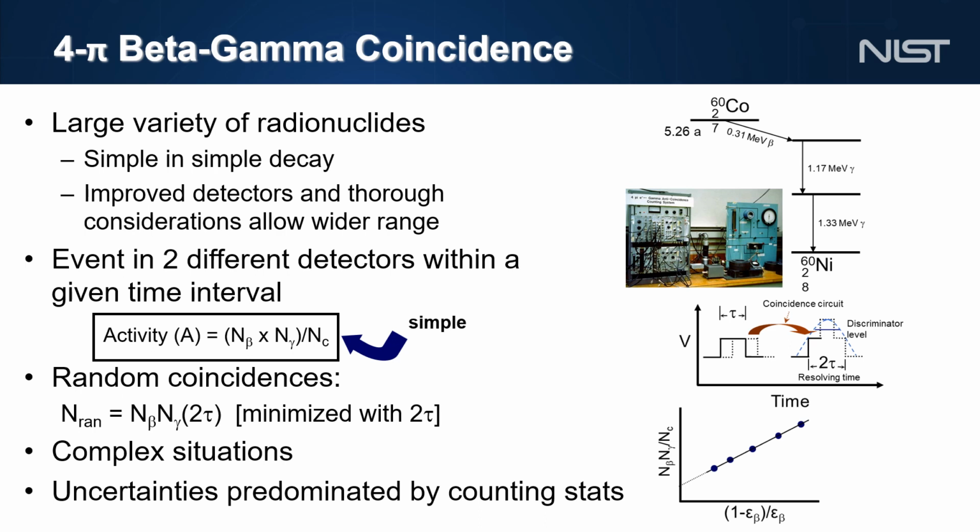A conventional system, such as that at the NIST, consists of a 4 pi proportional counter coupled to a pair of sodium iodide crystals for sensitive photon detection. The coincidence channel records an event only when it is detected by both beta and gamma channels. A crucial aspect is determining when a pulse occurs, which can be done using pulses directly from the detector or, more slowly, relying on energy dependence, noting the pulse only when it is a specific energy.